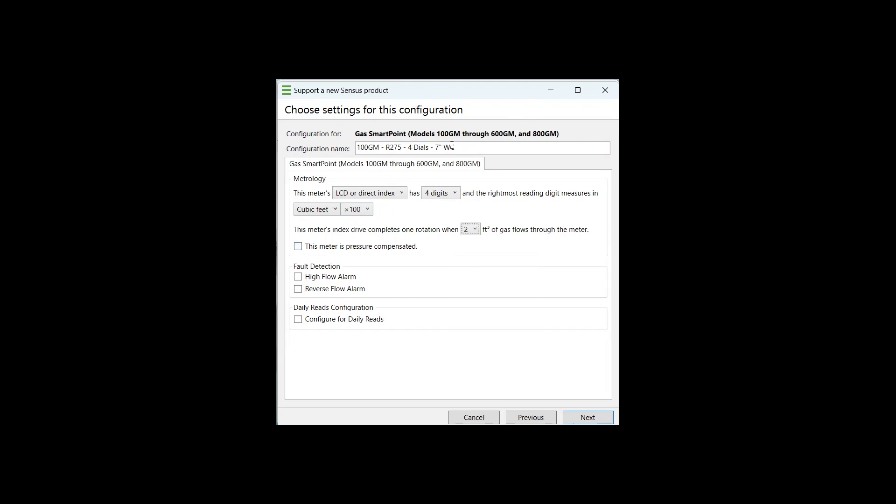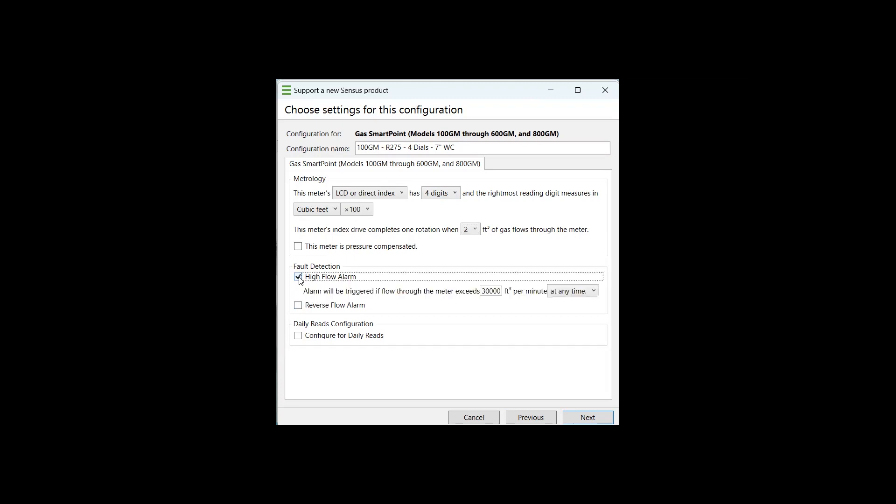Since we said that this meter is not pressure compensated, we're going to leave this unchecked. For any type of alarms that you would like to be applied to this smart point upon activation, that's going to be under your fault detection tab. We have a high flow alarm and a reverse flow alarm. We typically do not recommend applying these alarms on initial setup as a high flow alarm could be triggered mistakenly if you do not have exact parameters for each individual account. So you'll need to know how much gas has the potential to go through that meter at a cubic foot per minute at any time. We like to recommend that you leave this setting off, the high flow alarm off until you get some good consumption data to review and apply the appropriate parameters for that setting.